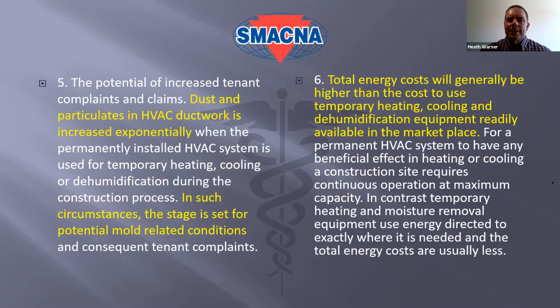Dust and particulate in the ductwork. This is another one you don't think about a whole lot. If you get all of that particulate in there, the stage is set for mold-related concerns, but also just customer complaints. I have one of my customers that I've always joked around with that when they build a building, they build it for life. If a customer comes back and complains to them 20 years later, they go back and fix it. So imagine a system that isn't cleaned out correctly, and you're continually going back, chasing your tail, or replacing a whole HVAC system because it was used during construction.